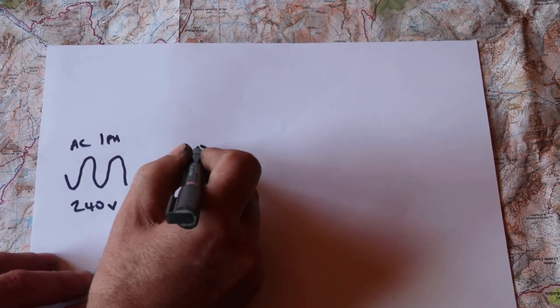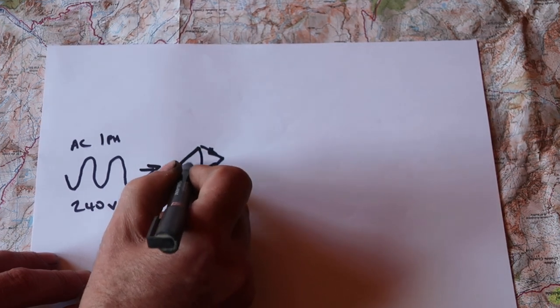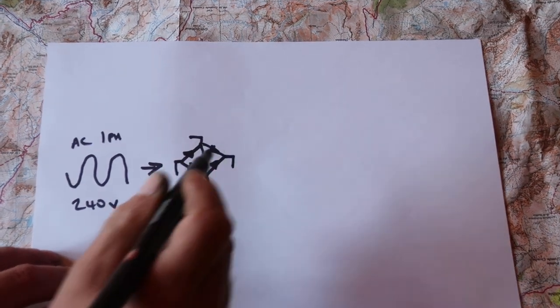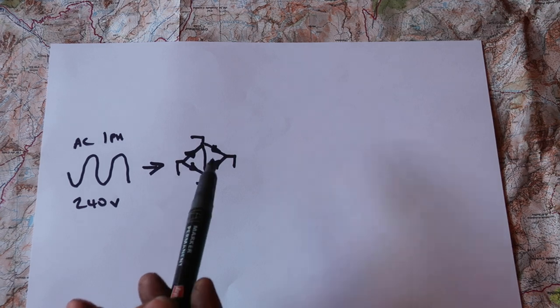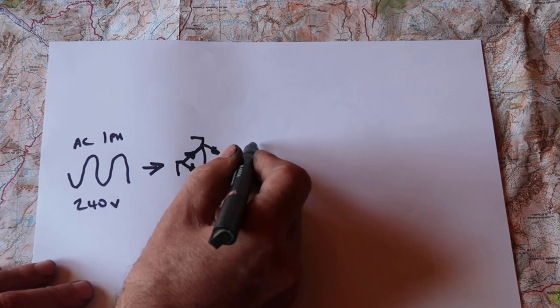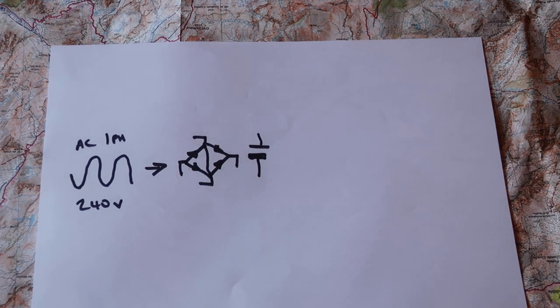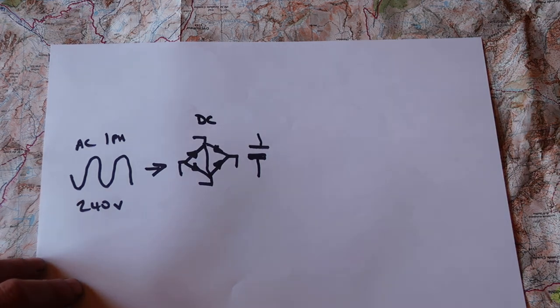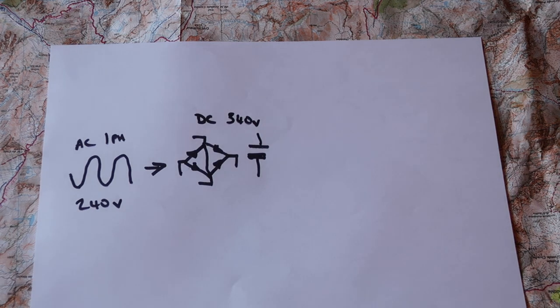Your VFD takes that and goes through a full bridge rectifier and some capacitors. That turns this into DC, 340 volts or thereabouts.